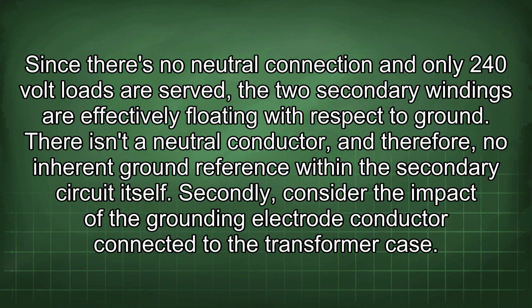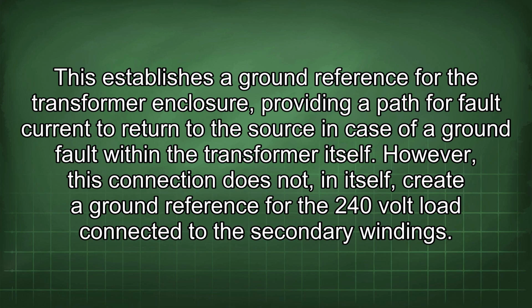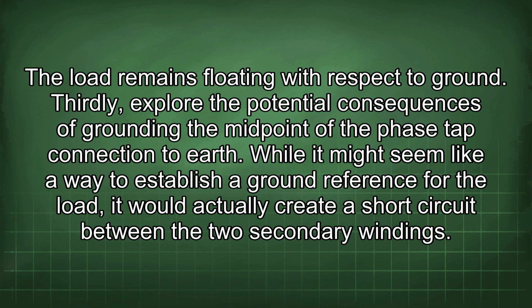Secondly, consider the impact of the grounding electrode conductor connected to the transformer case. This establishes a ground reference for the transformer enclosure, providing a path for fault current to return to the source in case of a ground fault within the transformer itself. However, this connection does not, in itself, create a ground reference for the 240 volt load connected to the secondary windings. The load remains floating with respect to ground.